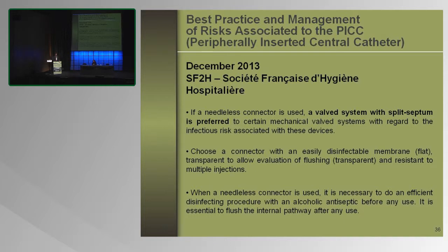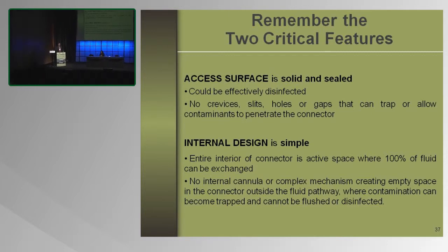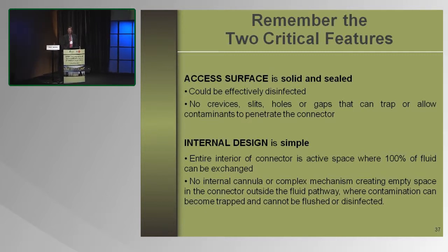So it highlights again 2 of the most important features of needleless connectors. So it's important to remember these two critical features. First is the access surface. Is it solid and is it sealed? Can it be effectively disinfected? There are no crevices, slits, holes, or gaps that can trap or allow contaminants to penetrate that connector.